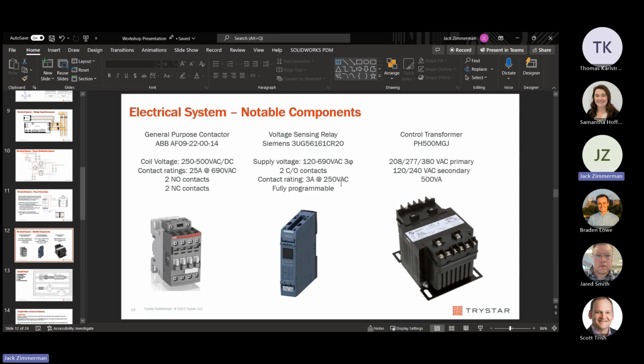But yeah, that's one of them, as well as this voltage sensing relay. This is the upgraded PRM I talked about. This thing can take anywhere from 120 to 690 volt AC. I would say it is flexible to any system we do, just because it's such a wide range and it's programmable, so I wouldn't worry so much about this. You just have to know that we have to program it per the application we use. And as well as that, the control transformer: voltage transformers are dependent on, believe it or not, voltage. So we would need to spec a control transformer that would work for the voltages we are going with. And I shared a document with the meeting that had a BOM with all of the dependencies for different voltage, current, all of these things.